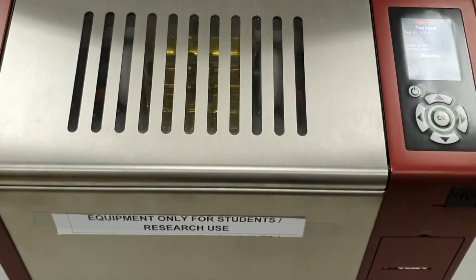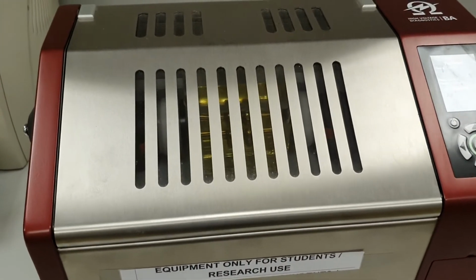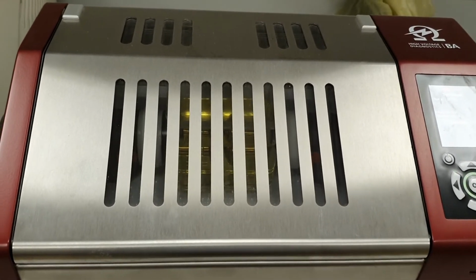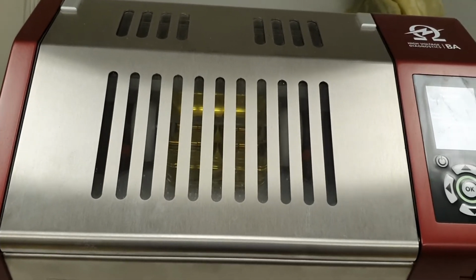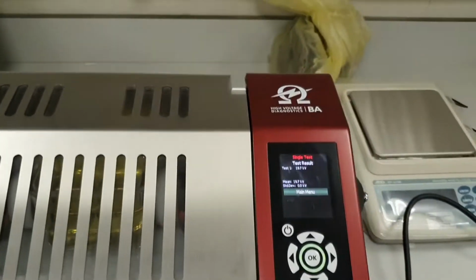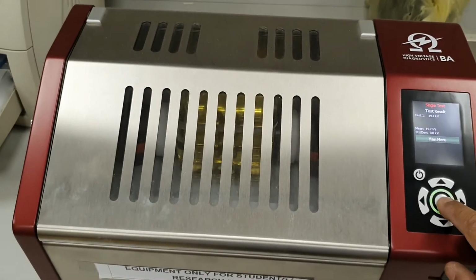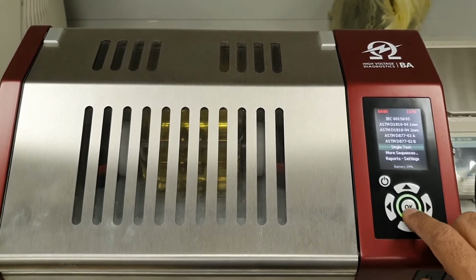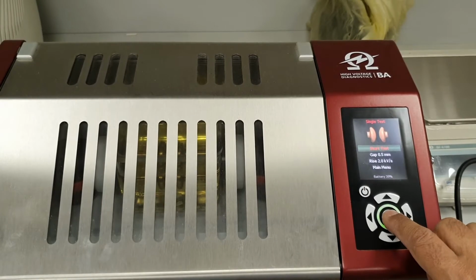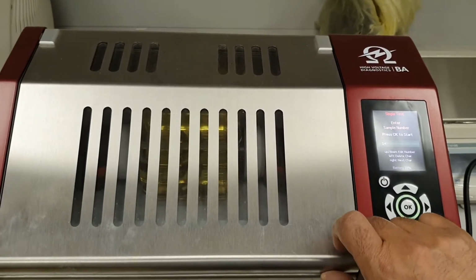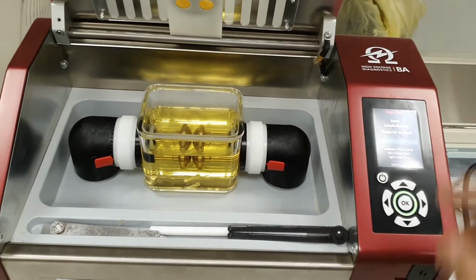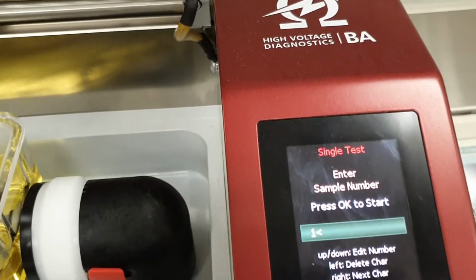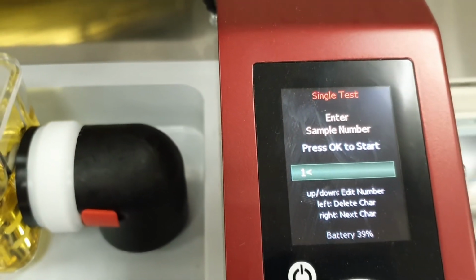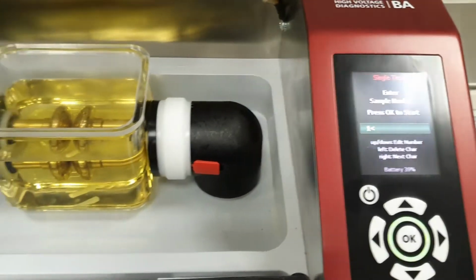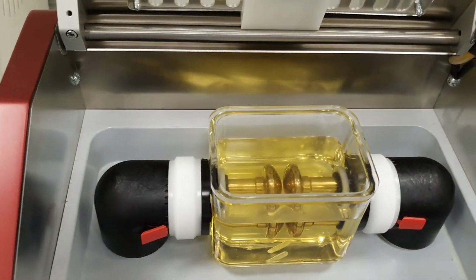Here you can see the main important thing is, because this is high voltage generating equipment that gives a maximum of up to 80 kilovolts, safety is very important. Now if I press this power main menu, then press single test, okay, then press the switch on, and now if I open this lid suddenly, the high voltage is turned off. It will switch off the high voltage. That's very safe. That is the most important safety factor for this one.